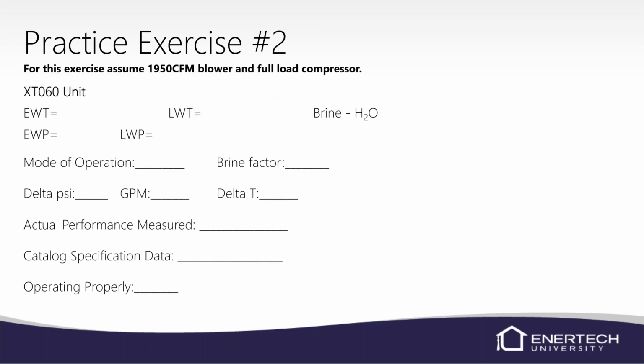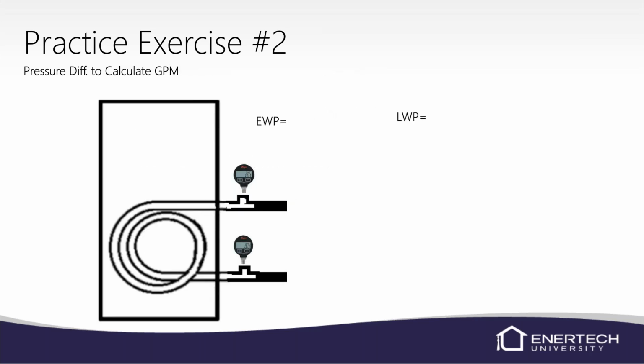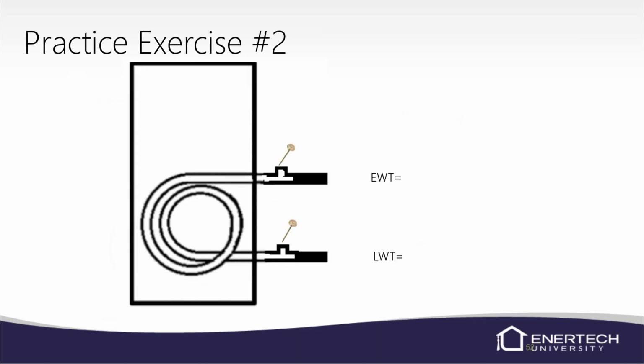We'll go through another exercise here. We're going to assume 1950 CFM, obviously XT060, so a 5-ton unit. Entering water pressure of 23.5 and leaving at 21. We just do the math. That's a 2.5-pound pressure drop.